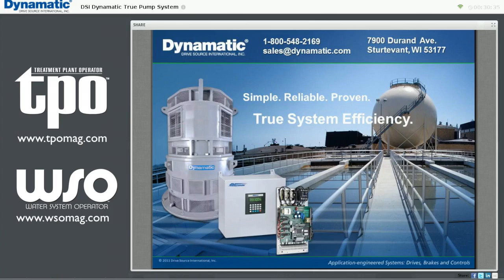We have another question from Miles: can you retrofit with existing motors? Absolutely. There are occasions where we do use existing motors to retrofit the eddy current drive. Because of the high available torque on an eddy current drive, we would have to evaluate the individual motor. But typically, a standard AC motor can be retrofitted onto an existing eddy current coupling. We have a question from Mr. Barnett: why would medium voltage seem especially suited to eddy current use? The best reason is that the eddy current drive is not operating on the system voltage — it's actually operating from basically a lighting circuit powering the controller. Therefore, we don't have any high voltage conversion devices, which considerably reduces our first cost.